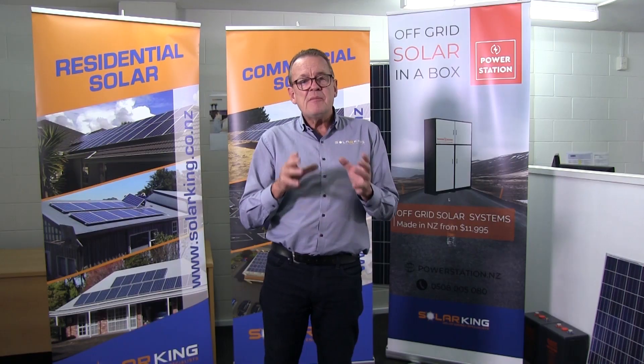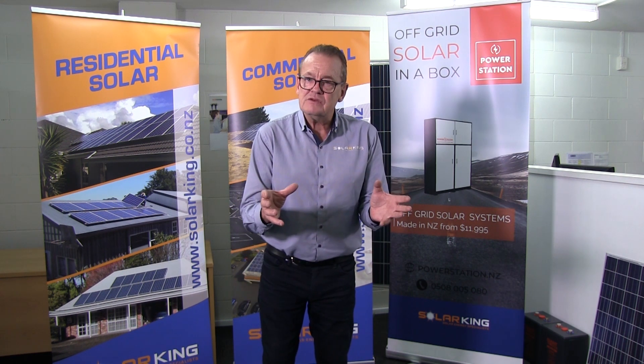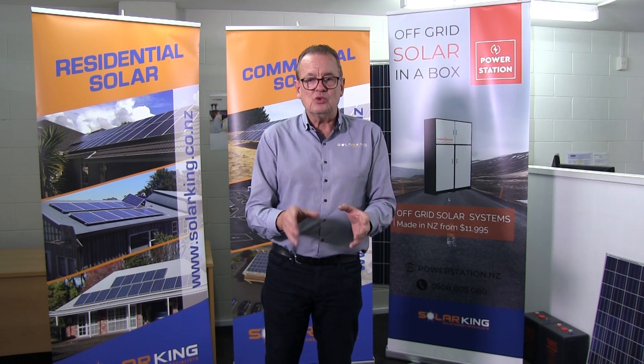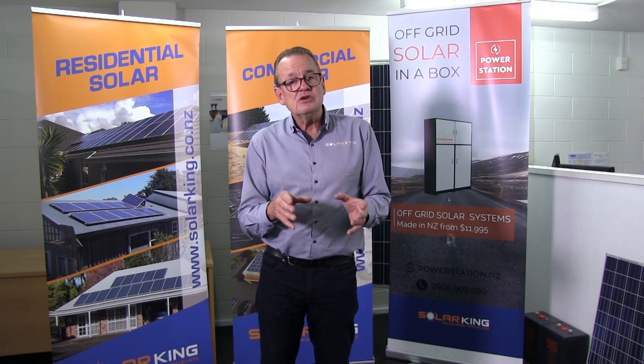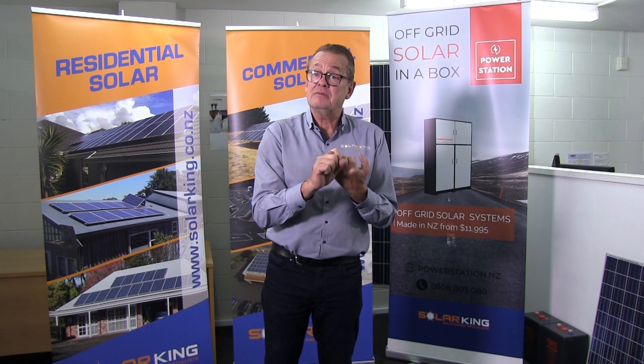A hybrid inverter, or a battery ready inverter, is a combination of the inverter I just described with a battery management system. This unit is able to connect to batteries — it does everything an inverter does, plus the surplus power that a normal inverter would send to the power company, this system sends to the battery where it's stored. The inverter controls your home's power so that your home is spending the solar power first, the battery power second, and only thirdly will it take any power from the grid.